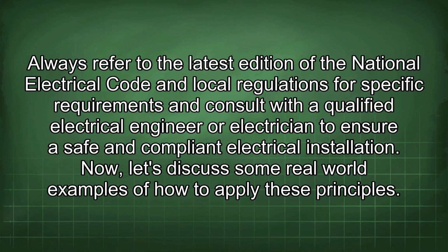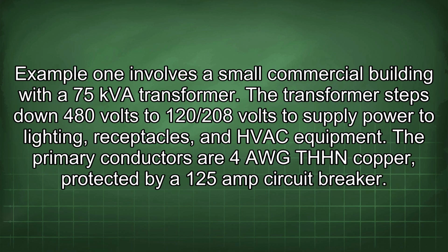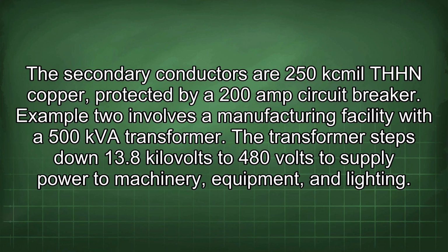Now let's discuss some real-world examples of how to apply these principles. Example 1 involves a small commercial building with a 75 kVA transformer. The transformer steps down 480 volts to 120/208 volts to supply power to lighting, receptacles, and HVAC equipment. The primary conductors are 4 AWG-THHN copper, protected by a 125 amp circuit breaker. The secondary conductors are 250 kcmil-THHN copper, protected by a 200 amp circuit breaker.